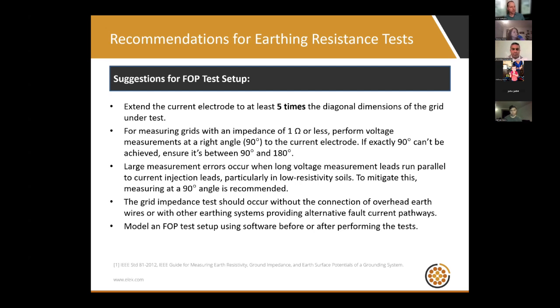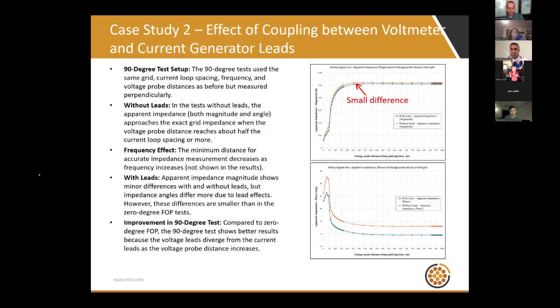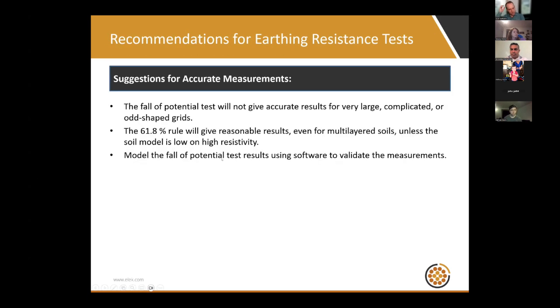And you should model your fall of potential test setup using software before and after performing the tests to validate the results. Please note and remember that the fall of potential test is not expected to give accurate results for very large, complicated, or oddly non-symmetrical shaped grids.